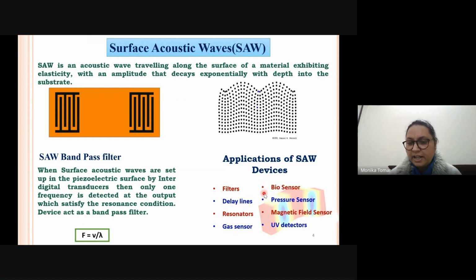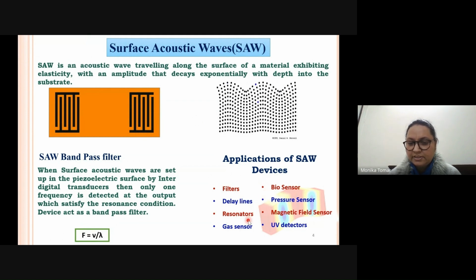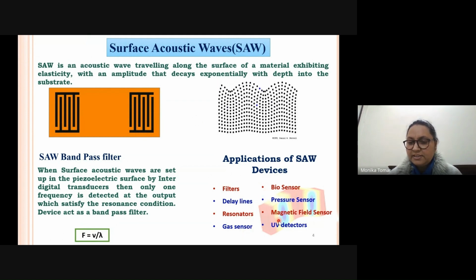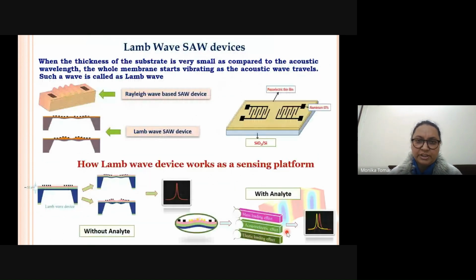So the SAW devices find a variety of applications like in filters, delay lines, resonators, gas sensors, biosensors, pressure sensors, magnetic field sensors, and UV photodetectors. In the present work, since we want to focus on sensing applications, we have moved on to the Lamb wave SAW devices. Now, what are Lamb wave devices? Lamb wave devices are those where the entire SAW device, that is the piezoelectric substrate and the two transducers, are fabricated onto a membrane. If you reduce the thickness of the substrate and make the entire device on a membrane like this, then the entire membrane moves while the waves are propagating.